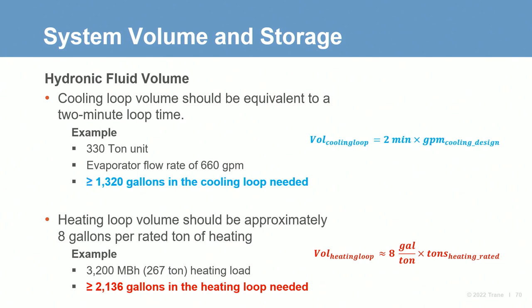Thanks, Dan. Building on what Dan mentioned earlier about loop volume, to ensure occupants remain comfortable during transients, special considerations are needed in the cooling and heating hydronic design. The guidance for cooling loop fluid volume remains at a minimum of 2 minutes. The heating loop is subject to additional transients such as defrost that can send cold fluid through the air handlers, quickly affecting occupant comfort. To ensure proper hot water supply, and based on our experience in the EU to date, the heating loop fluid volume should be about 8 gallons per heating ton.